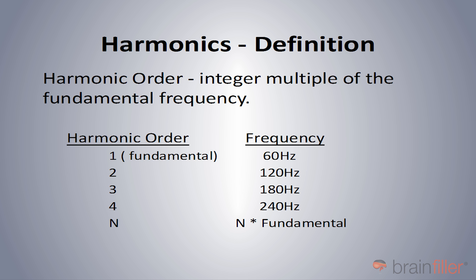So the first harmonic, or the fundamental, is going to be 60 Hz. A second harmonic would be 2 times 60 Hz — that would be 120 Hz. Third harmonic would be 180 Hz, and so on. And if you're in a country or an area with a 50 Hz power system, this would just be translated to 50 Hz. The first harmonic would be 50 Hz, second harmonic would be 100 Hz, and so on.